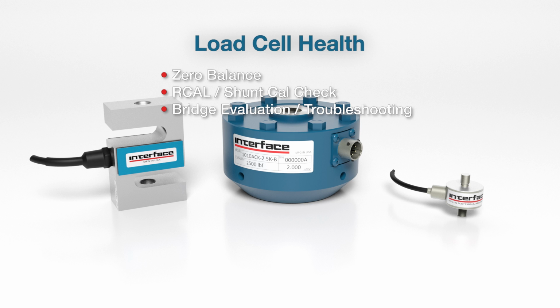Number one would be zero balance. If the load cell has been in use for a while, it'd be good to do a sanity check on the load cell. The zero balance is going to be a good check to see if there's been any potential overload or damage to the load cell. If that zero balance is shifted, let's say you have an increased zero balance, let's say it's a negative, it's shifted up or down some way from the nominal, that's an indication of potential damage.